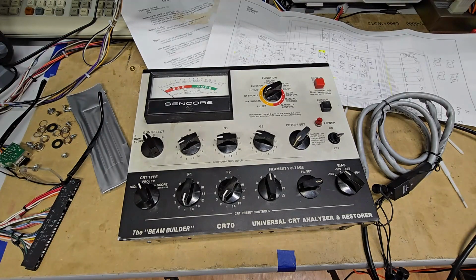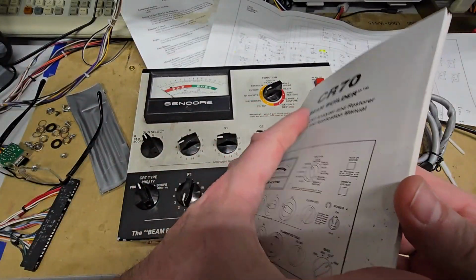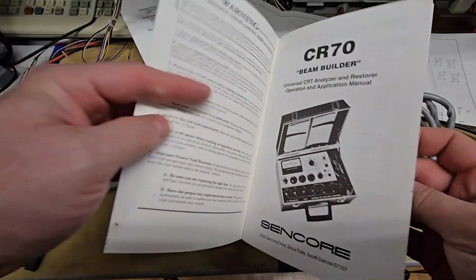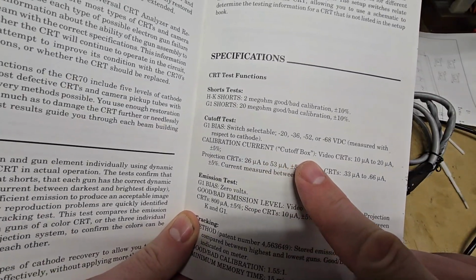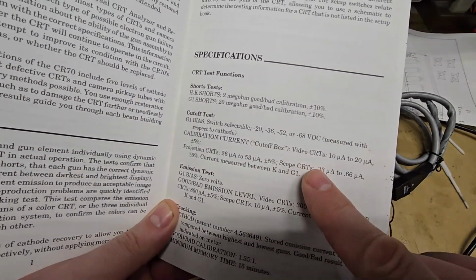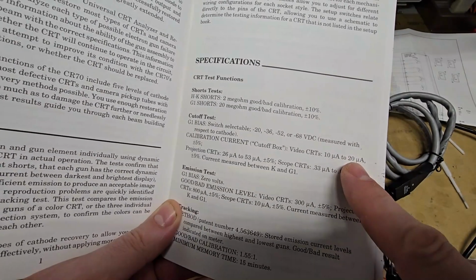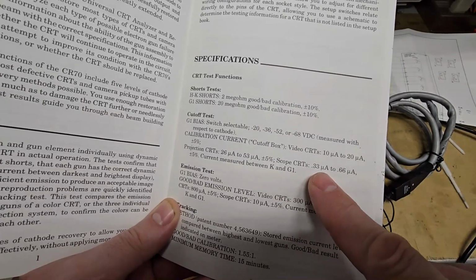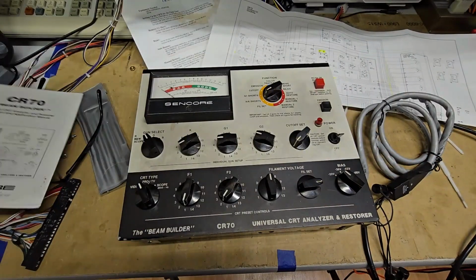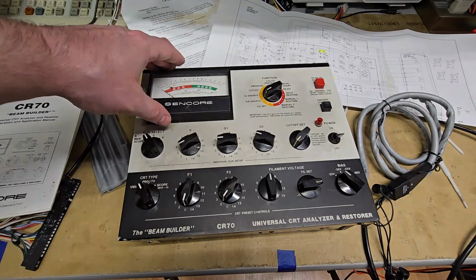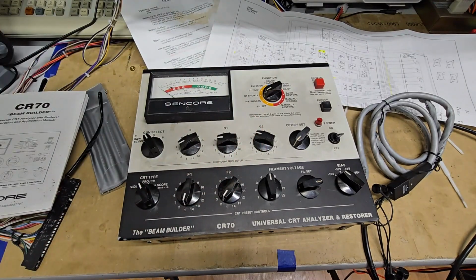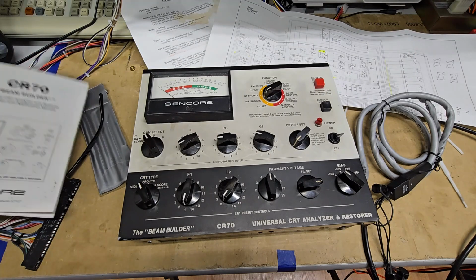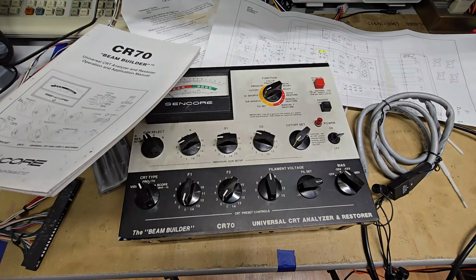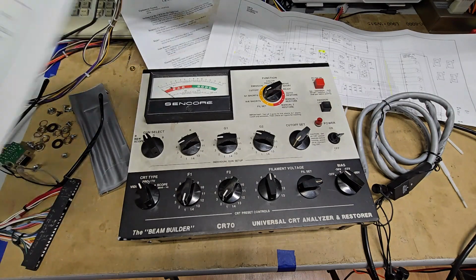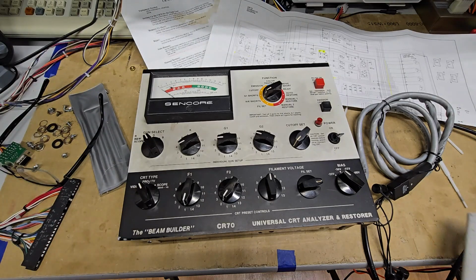So I don't know what those things are supposed to be adjusting, but that's what I figured I would show in this video. The only thing I have is the manual, and the manual does give some kind of clues, like calibration current 10 microamps to 20 microamps for video CRTs, and then for projection, I think part of it is the adjustments adjust the meter and what it's reading based off of what it's outputting versus adjusting what it's outputting. But I don't know. That's what we're going to find out. I'm going to try to calibrate it to the best of my ability with limited knowledge of what the heck those adjustments are actually doing.